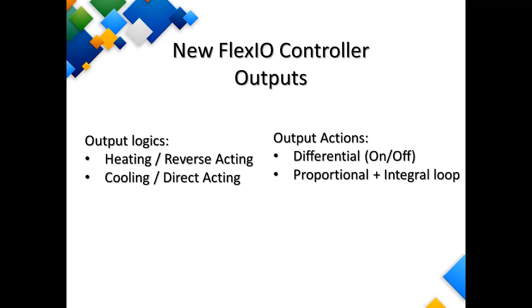Now, we have added a few extra features on this, such as overrides on the outputs. So we can control an output any way we want, let's say whether it's based on pressure or on temperature, something like that. And then if we choose to, we can override that output to a specific value based on the outside temperature. So you could say if it ever gets hotter than this outside, then either turn it on or turn it off or whatever, as we will see on the software demo. And you can also override the outputs based on occupancy as well, because maybe you want the occupancy of a building to turn something on or off.